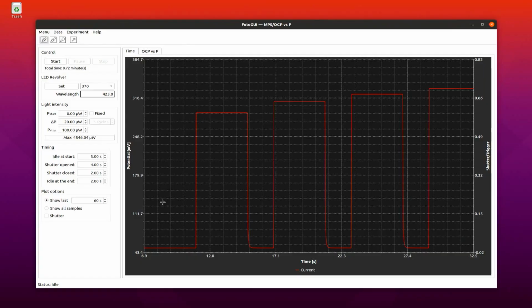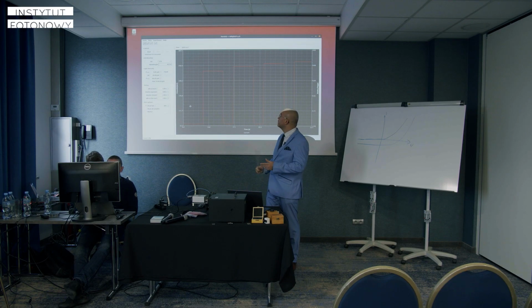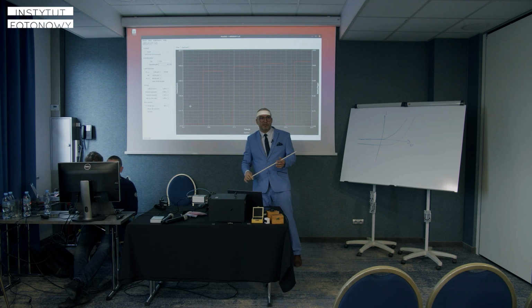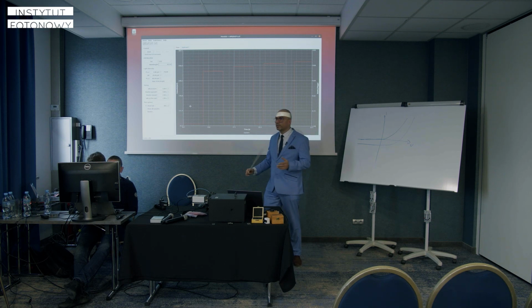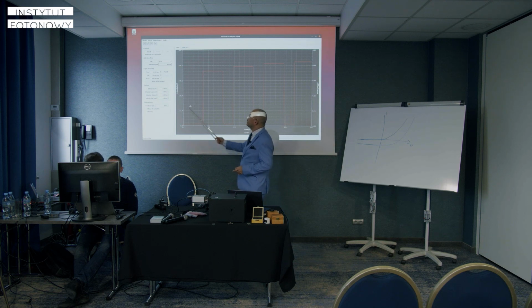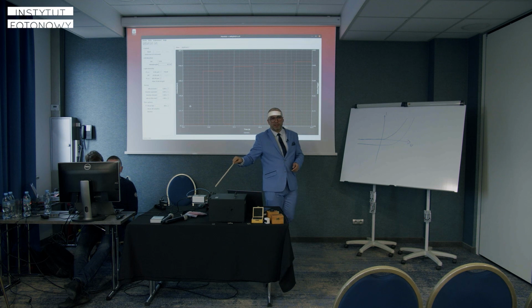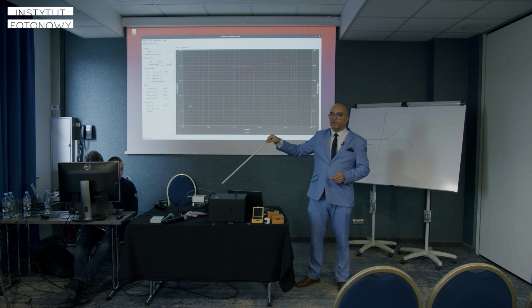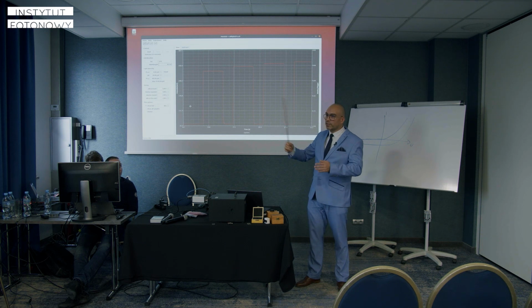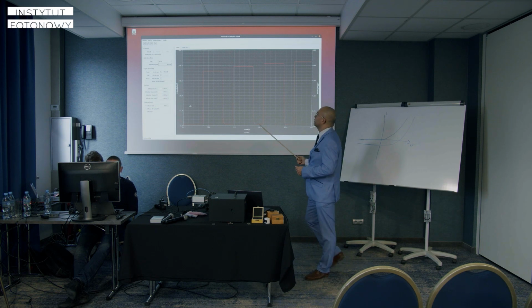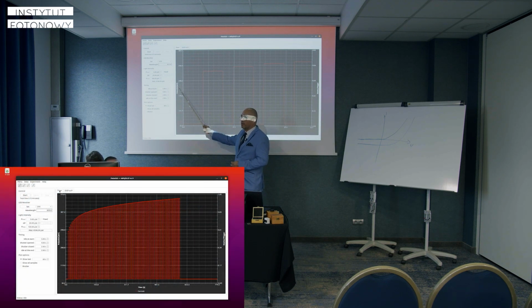And what the program does, we also can define some time slots, time windows, and we give 5 seconds to the circuit to get stabilized after we start the experiment. We can give 10 seconds to get stable if the sample is charged before, we can increase some time to let the sample discharge. Shutter open, shutter. There is no mechanical shutter like in the case of the large photoelectric spectrometer. We control it just electrically. We don't have to use a mechanical shutter, this is just a name for this feature.